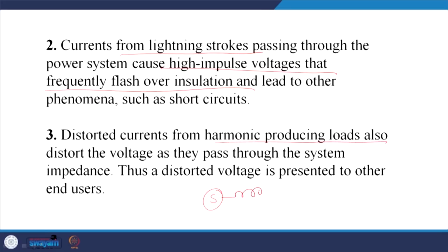Distorted current from the harmonic producing load also distorts the voltage, since you have a source inductance and you have a diode bridge rectifier. Though these will distort the current with harmonics, due to the source inductance there will be 5th and 7th harmonic voltages also. So, that will distort the voltage as the current passes through the system impedances. Thus, distorted voltage is presented to the end user. If someone is here, he will be getting a distorted voltage. So, now who is responsible, the utility or this neighbor? This is a matter of perception.